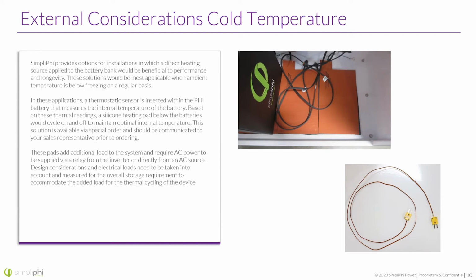So, design considerations should always be followed here. You're talking about a bigger electrical load. I don't have those specific figures right now on me, but it is significant enough. And definitely if you're talking like a 2 or 3 battery system, it's pretty significant if you have a lot of cold temperatures you're dealing with. So that's always something to consider when using these external heating pads, is that they do use power, and it will be part of a load, or be a load in the system that needs calculations.